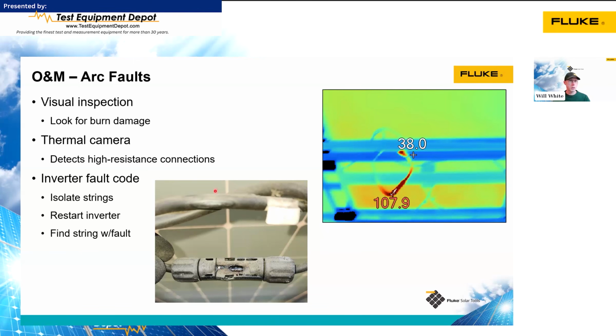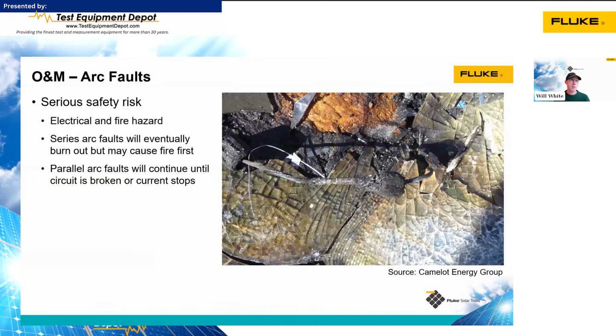And I just want to point out this picture. This looks like it may have started as a series arc fault. You can see that gap right here between the positive and the negative connector there. And then I would guess that this heated up and melted to this connector here, and then it became a parallel arc fault. So you kind of have 2 different things going on there, neither of which are good for system performance and safety. So arc faults, big safety risk. They can cause hazards. They're arcing, so there's energy going places we don't want it to go. Series arc faults are eventually going to burn out. Parallel arc faults are going to keep going until the circuit's broken and the current stops.